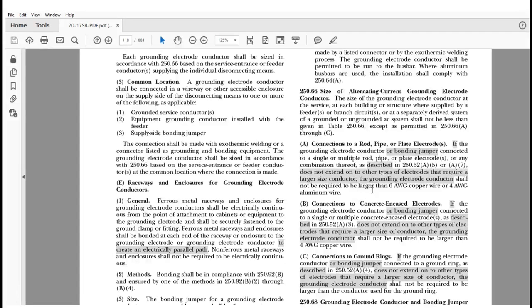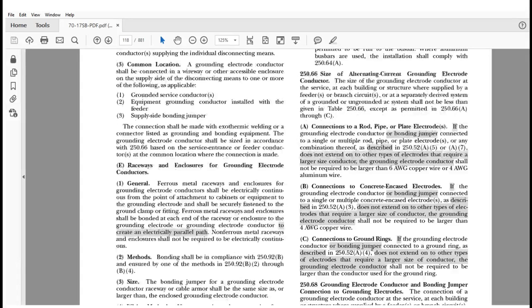All right. And the same thing with the ground ring. Remove that sole connection. So here's the real good part about this: the misconception in the past when it came to things like daisy chaining. The grounding electrode conductor was the sole connection to the ground ring, the sole connection to the rods, pipe, or plates, or to the concrete encased electrode in accordance with 250.66 A, B, or C, had a provision for the size it had to be, and you didn't need to go to Table 250.66 to do the calculations for the conductors there. You didn't need it.